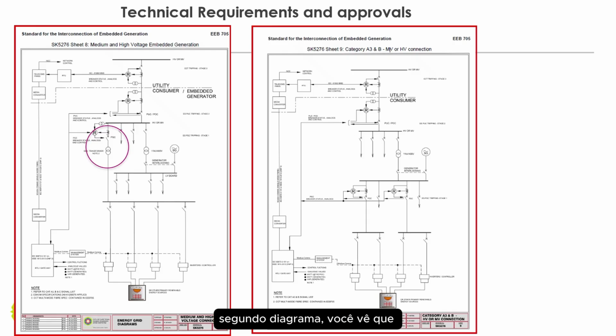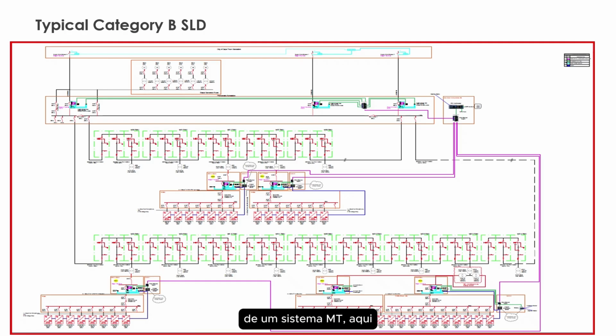But then with the second drawing, you will see we have introduced what we call stage 1, stage 2, and stage 3 protection. Stage 1 is on the LV side of the customer's network, where those breakers need to be automated so that they can trip for any out-of-bounds conditions. Should that not trip, we go to stage 2, which is the customer's MV breaker. And if all of that fails, stage 3 is where we, from the City of Cape Town, are able to open our supply breaker to the customer, and the entire installation will then be switched off. These are the protections that we can ensure for any out-of-bounds conditions for the greater than 1 MVA systems.